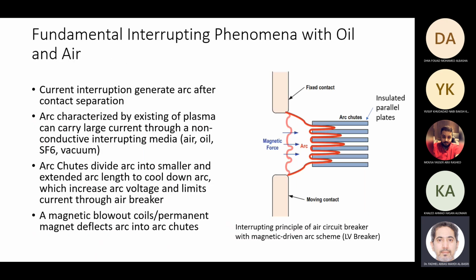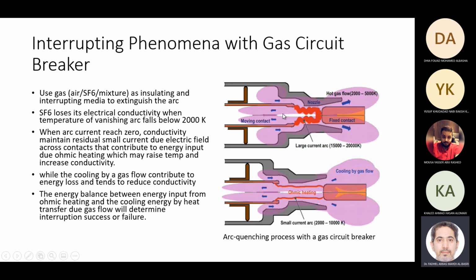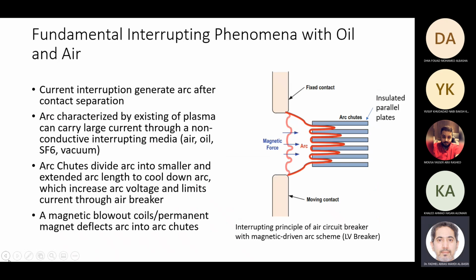So I'll show you these theories now. Let's say this is the fixed contact of the breaker, and this is the moving contact. Suppose now they were closed, and you push this one to open. The arc can be forced by air, sometimes forced by magnetic force, towards the arc splitter, or arc chutes.